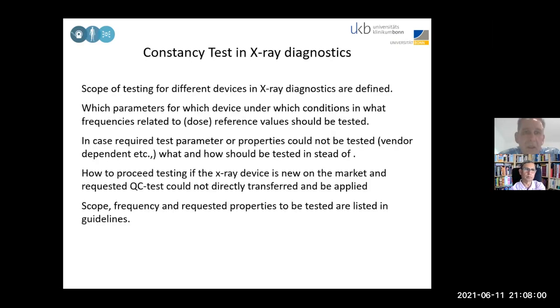So yeah, what is the scope of testing? What happens if you are testing at a different frequency, or if you have something which could not be tested, as I told, or if you have maybe a very new device which is not in a guideline? You have a new X-ray machine which has no guidelines, or you have only a few parts which you could do. So talk to the vendor again, and there is something which is coming along in my talk. It will be called the NEMA, and in the NEMA, the vendors or the manufacturers usually have stated how their machine works and how the parameters or properties are actually going to be measured.